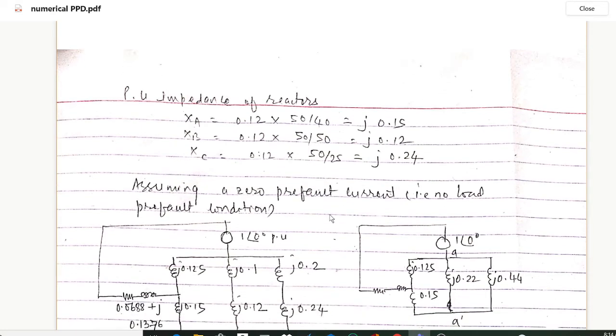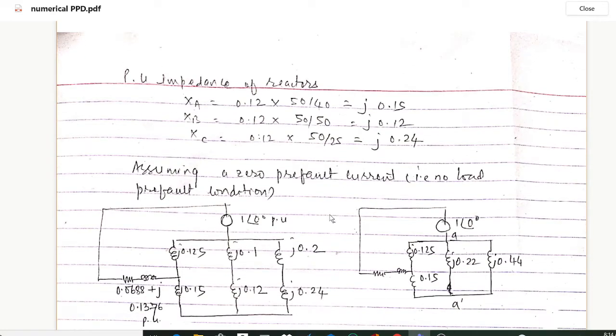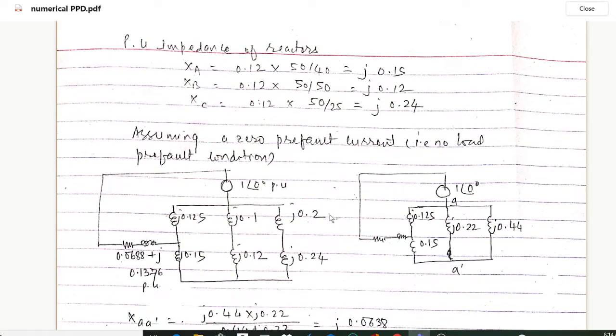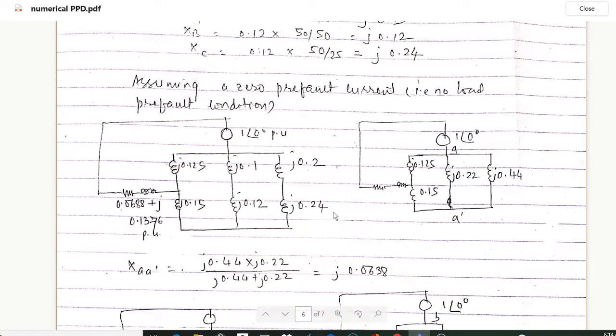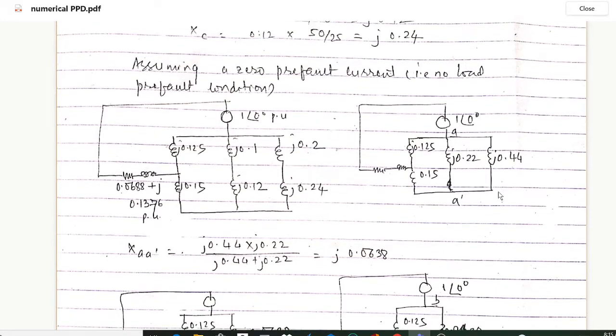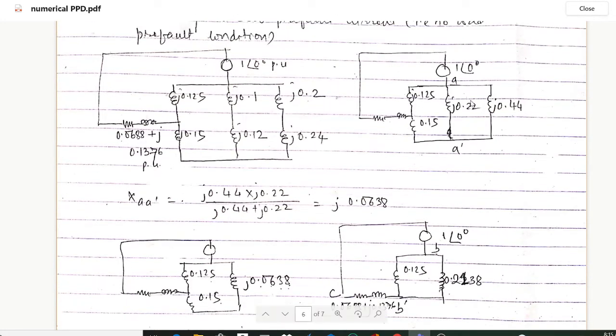Assuming zero pre-fault (no load) current, the reactance diagram is constructed by substituting all values. In the diagram, j0.1 and j0.12 are in series, giving j0.22. Similarly, j0.2 and j0.24 are in series, giving j0.44.